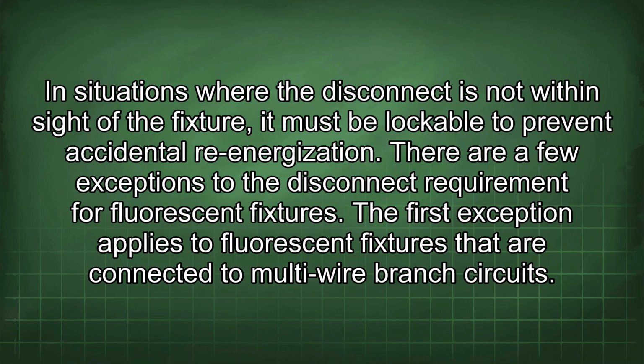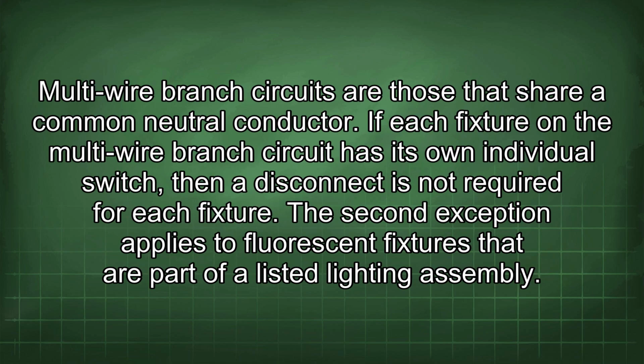accidental re-energization. There are a few exceptions to the disconnect requirement for fluorescent fixtures. The first exception applies to fluorescent fixtures that are connected to multi-wire branch circuits. Multi-wire branch circuits are those that share a common neutral conductor. If each fixture on the multi-wire branch circuit has its own individual switch, then a disconnect is not required for each fixture. The second exception applies to fluorescent fixtures that are part of a listed lighting assembly.